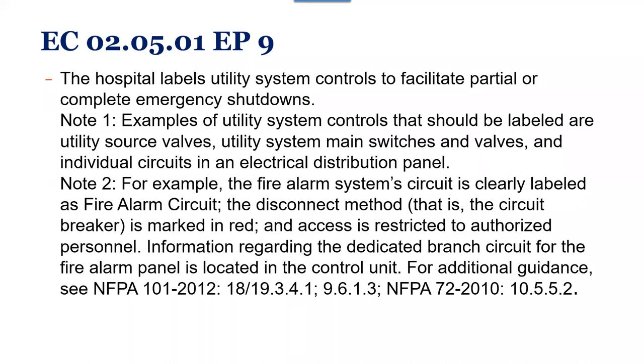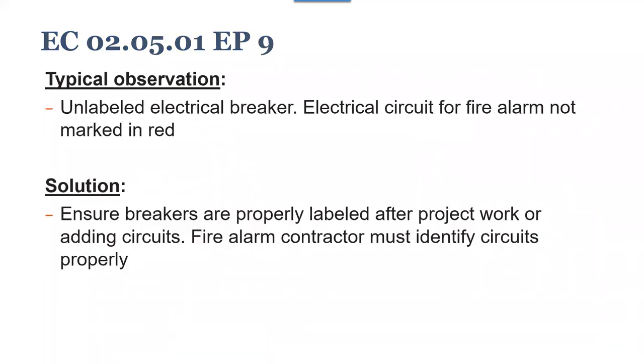And then finally, EC 02.05.01 EP 9 - the hospital labels utility system controls to facilitate partial and complete emergency shutdowns. Pretty much the number one observation at that EP is unlabeled or mislabeled electrical circuit breakers. Electrical circuit breaker for the fire alarm, not marked in red - that's not very common anymore, you guys have gotten that under control. But, labeling breakers, or not labeling - maybe it says it's a spare, but it's on, because the electrician is now using that spare breaker but didn't update the legend. That would be another example.